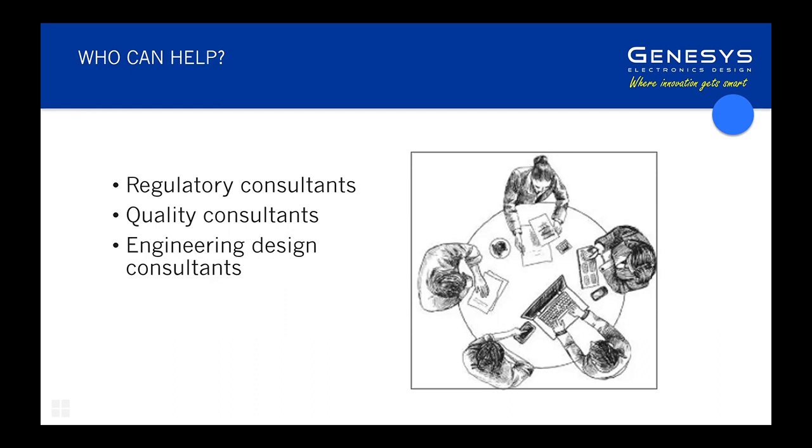We're all learning. I think Kevin's scratching a little bit deeper below the surface, and we could go to a great deal of depth in some of the aspects that you need to deal with and some of these subtleties, and it does get a little bit convoluted when you go down this path of particularly the hazards introduced, and if you have hazard risk mitigation measures in software, does that risk mitigation in software cause a new risk at the system level? So the whole thing becomes iterative, and it looks as though you could go on forever, but ultimately you have to bring it to a conclusion.